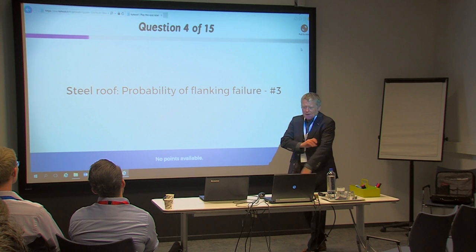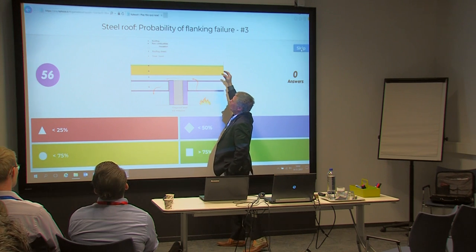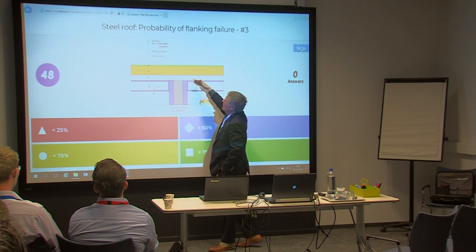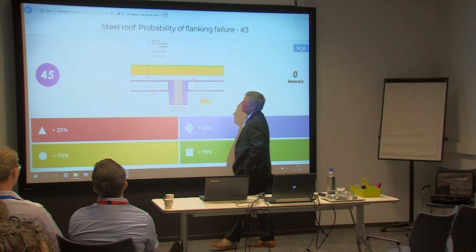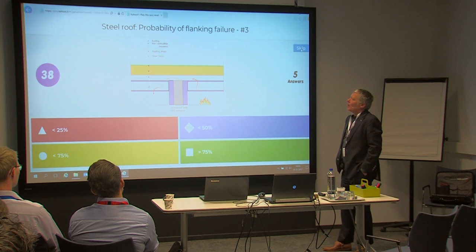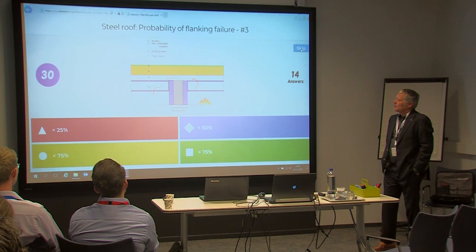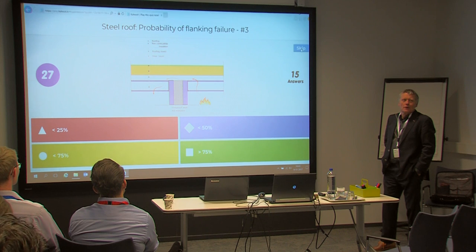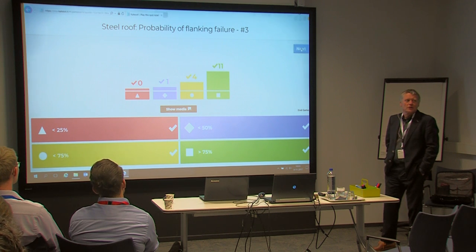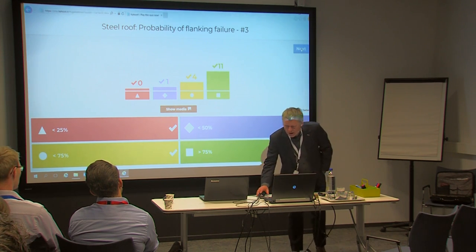Another roof detail: a situation where non-combustible layers are used but the profile steel plate goes over the compartment wall, allowing possible convective heat transport. The four intervals are 0–25%, 25–50%, 50–75%, and 75–100%. Results show the group assigns a much higher failure probability in this case, which seems expected.